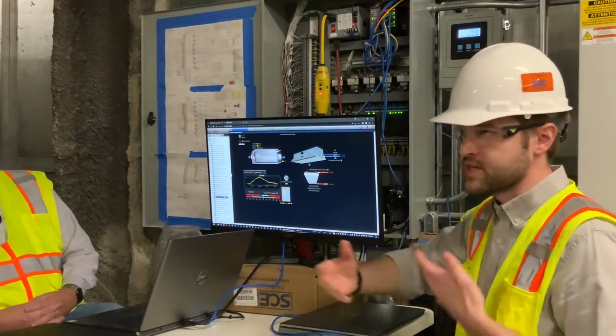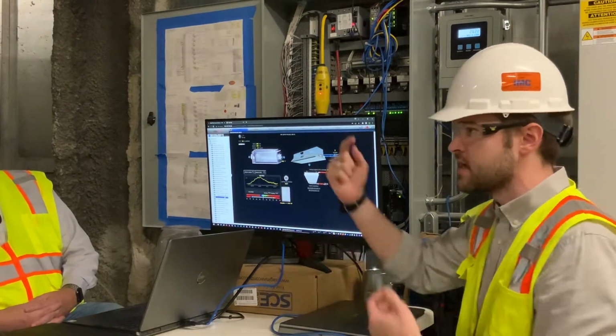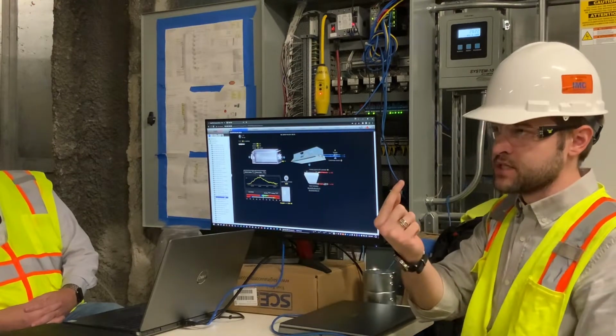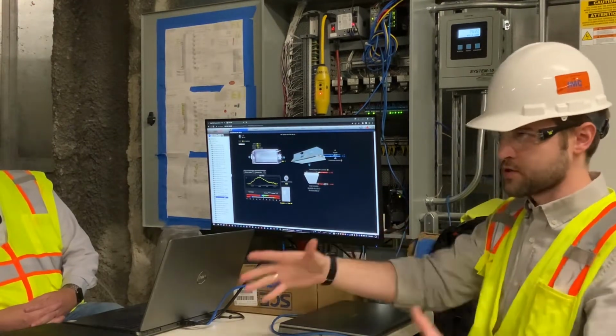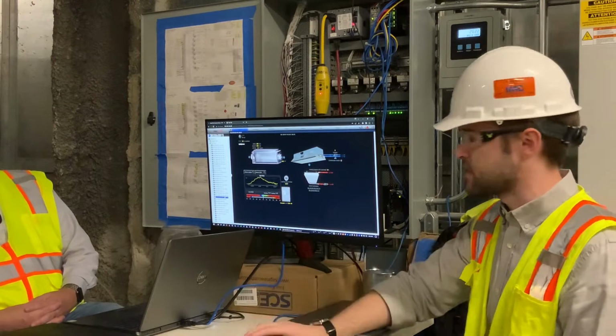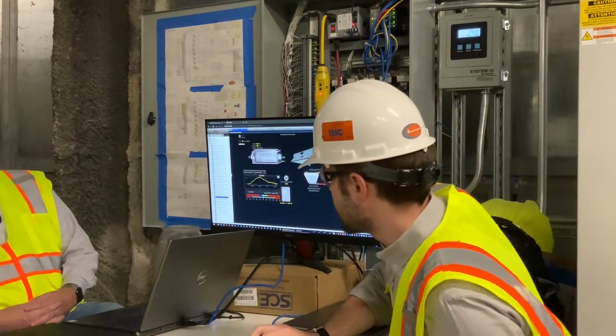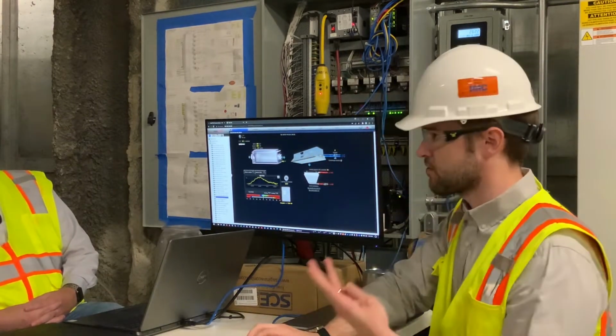So the temperature sensor goes back to one of the VAVs. Over the network, it sends that information to the next VAV, to the next controller. Also, they're all controlling to the same set points at the same time. In this case in particular, there's actually 3 controllers in this room.